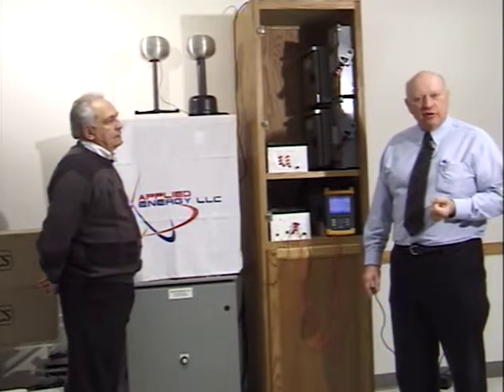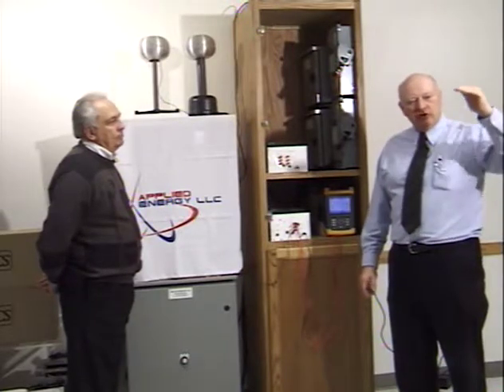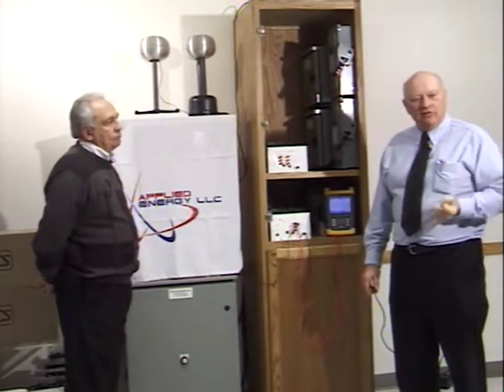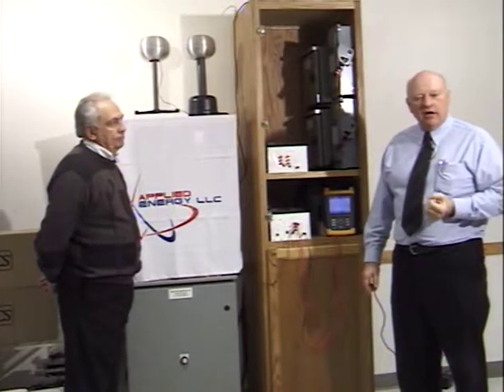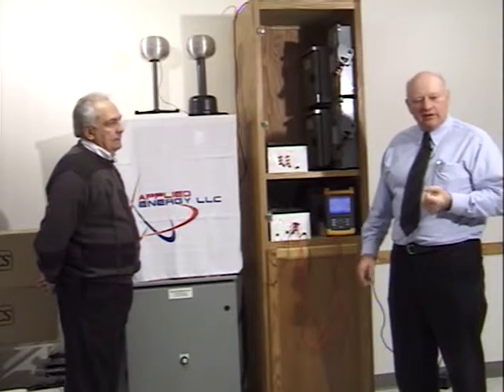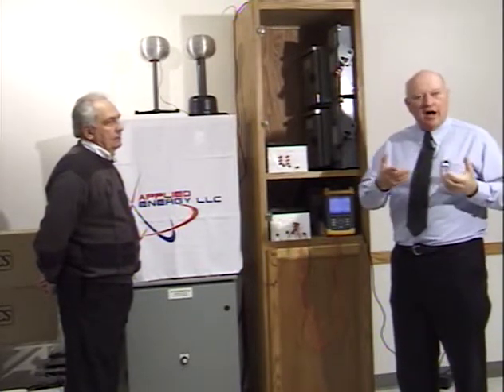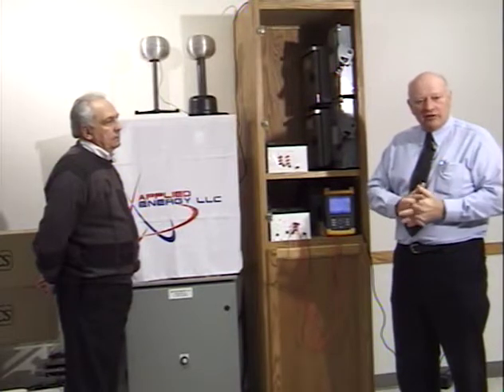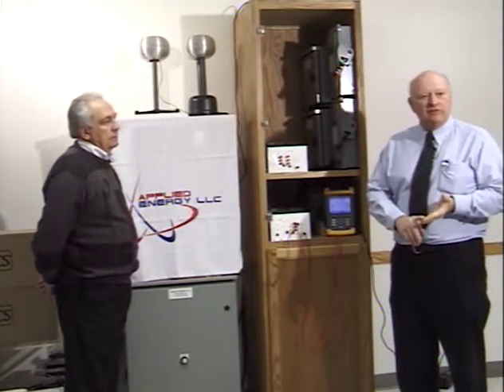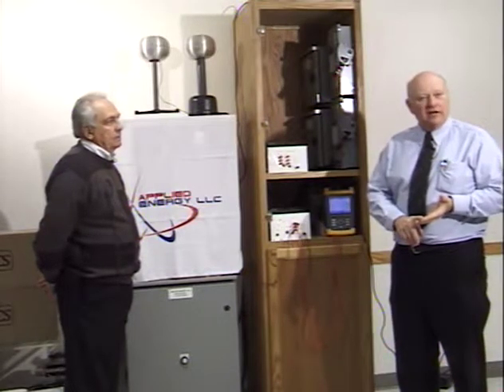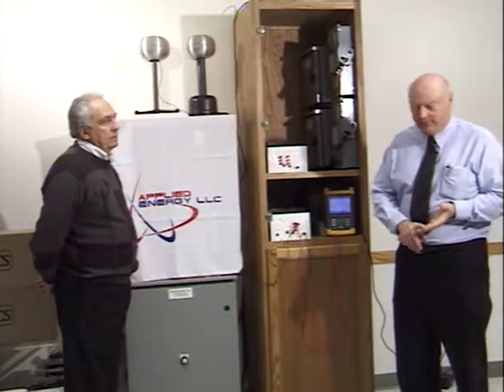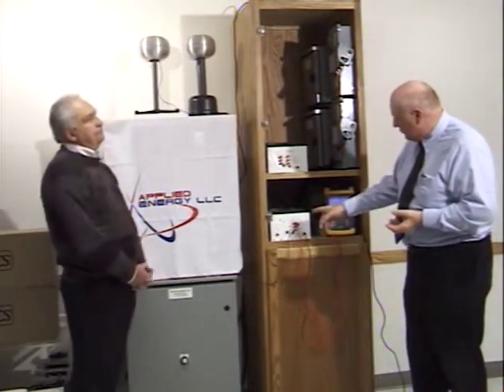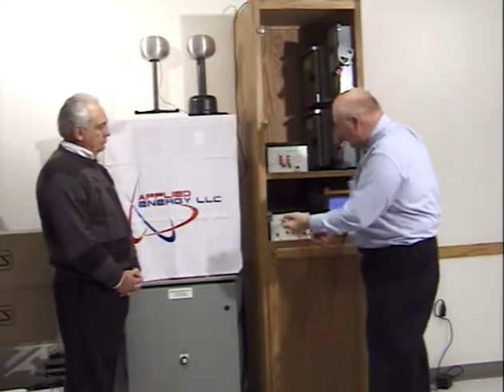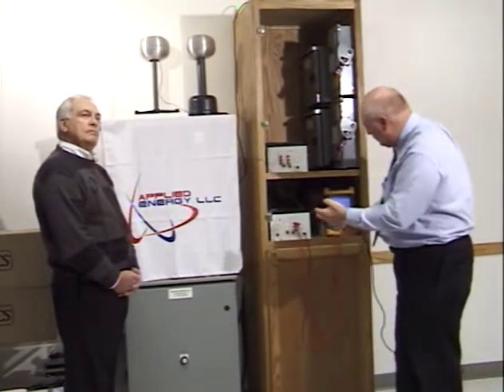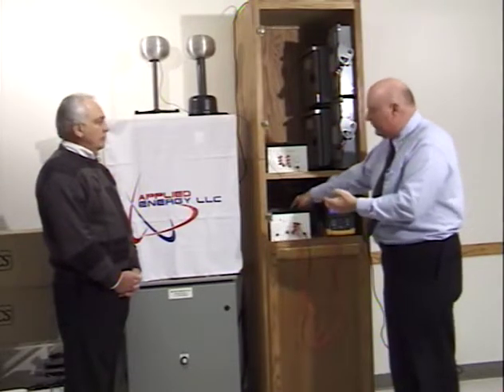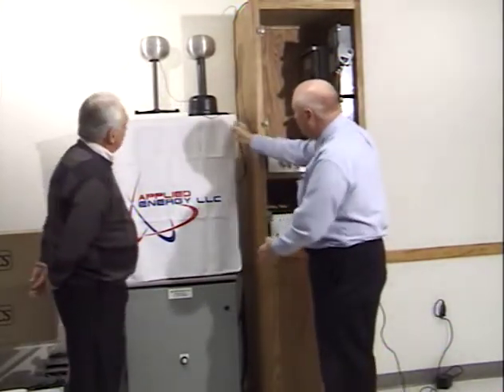Most technologies of transient voltage suppression allows voltage to get very, very high before it engages to try to invoke a correction. When it tries to invoke a correction, it takes that high voltage spike, converts it to a high current surge. Manufacturers have various ratings like 20,000 amps or 50,000 amps. We don't believe it's a good idea to put a very high current on your ground system. We're going to actually show injecting 200,000 volts directly to one lead of our running three-phase motor from our 200,000 volt Van de Graaff generator.